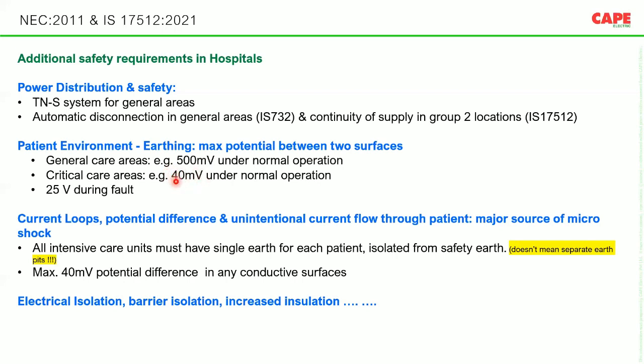You see, 40 millivolt is a negligible voltage, but more than 40 millivolt itself sometimes is deadly for a patient. And during fault condition, the potential difference must be limited to less than 25 volt. So very important: supplementary protective equipotential bonding.